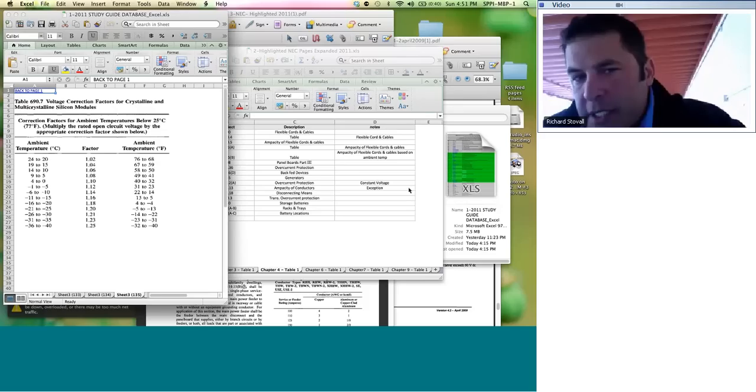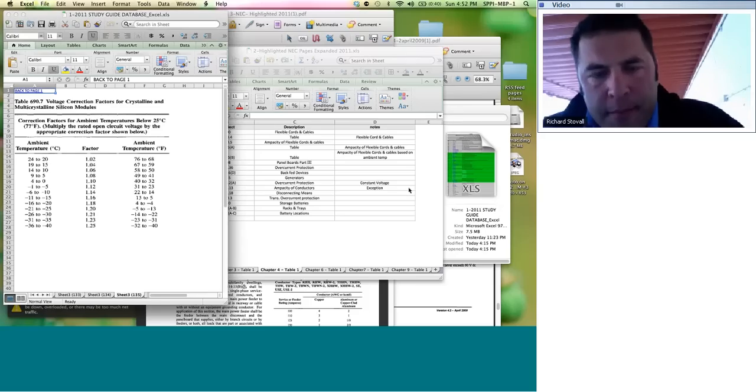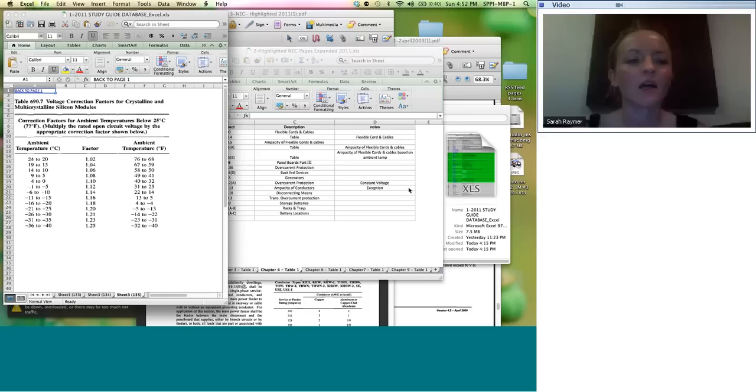Oh, you mean the one plus, utilizing it as a percentage versus an absolute value for voltage? That's probably what it was. Basically, the maximum system voltage is the VOC times your low temperature minus your reference temperature, which is 25 degrees, times your temperature voltage percent coefficient, times the number of modules in the string. In his formula, he had a 1 plus in there, and that kind of threw me for a loop because I hadn't seen it done that way before.